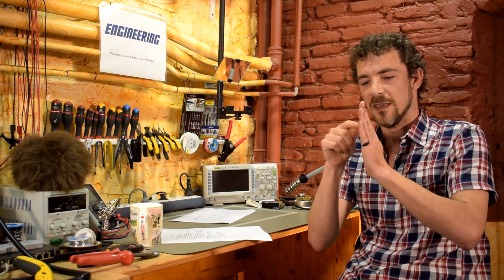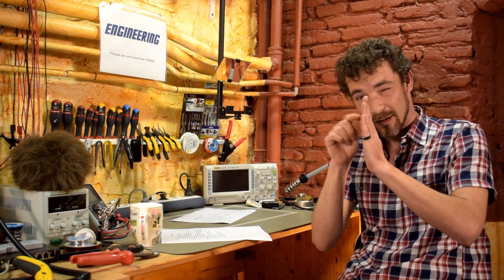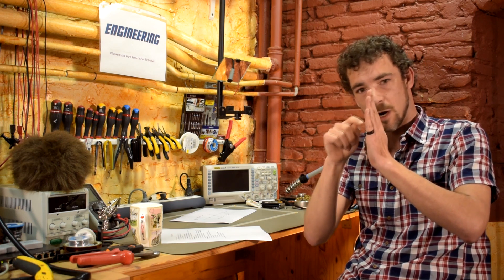And the final disadvantage to HVDC is circuit breakers. So when you have a circuit breaker, you can think of it like a switch. You have two metal contacts inside that breaker. And when the breaker is closed, they're pressed together and current will flow from this point to this point. And when you have these two contacts, and when you start to pull them apart, there's this massive voltage across them. So in between the contacts is something like air or gas or certain types of oils. In any case, it's an insulator. So you start to pull these contacts apart, but because there's this massive voltage across the contacts, sometimes that will cause the insulator, the tiny thin little layer of insulator between them, to break down due to the high voltage and start conducting. So as the contacts separate, that little arc actually just grows bigger because it's essentially like a wire connecting the two contacts together. And of course, arcing is very bad and causes all sorts of problems.